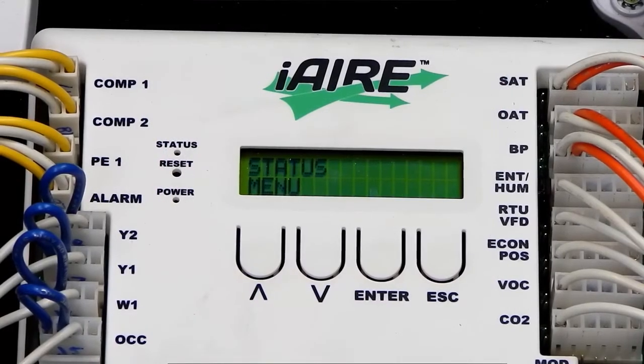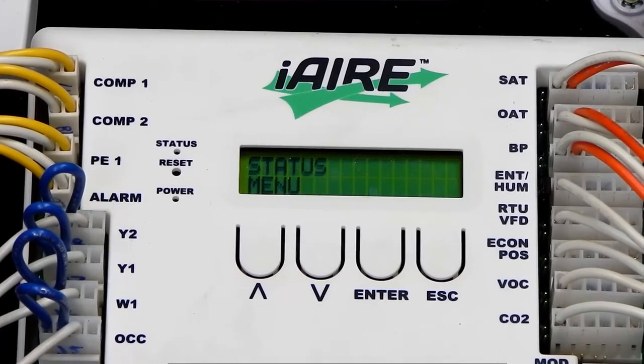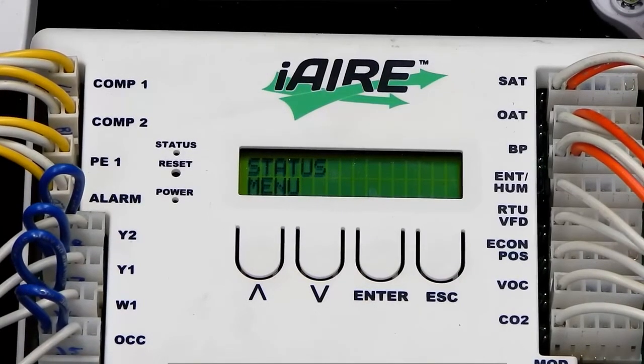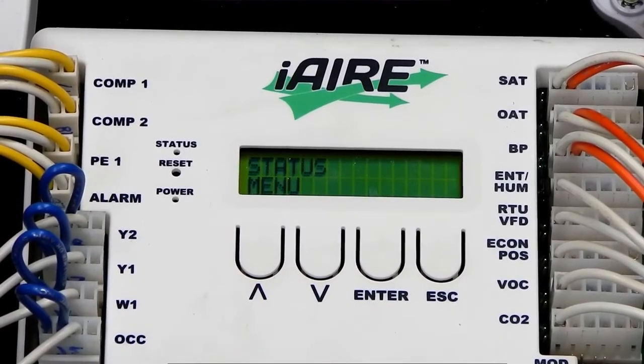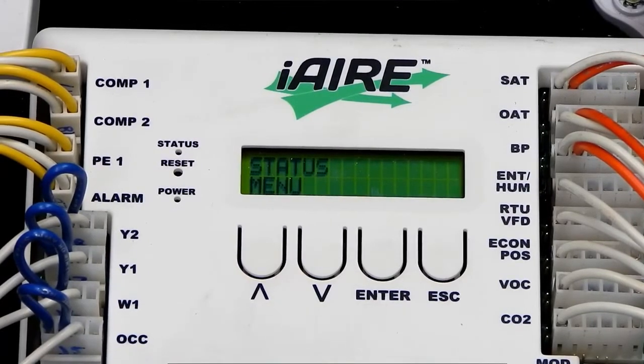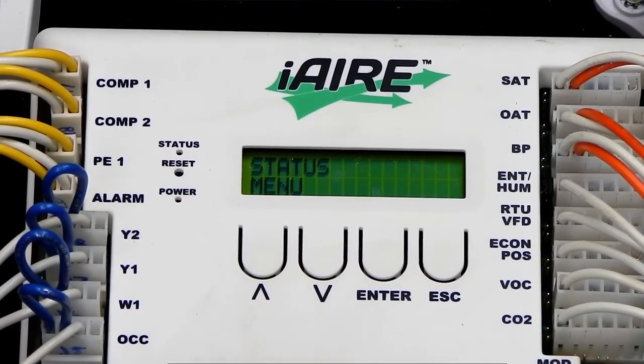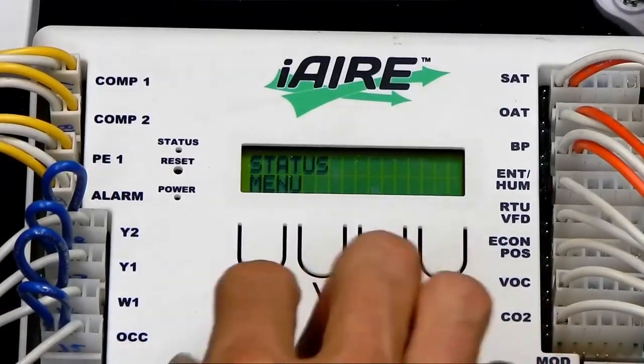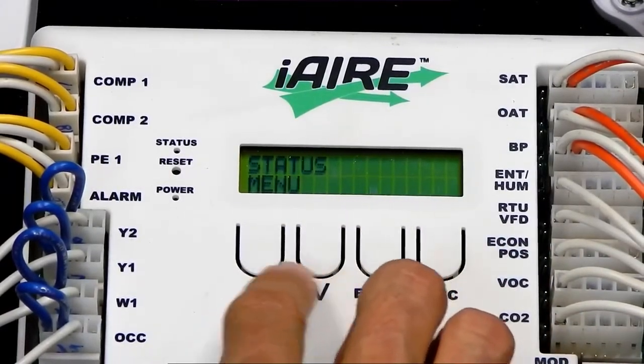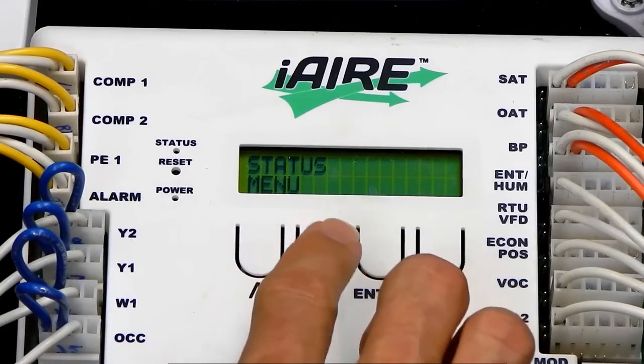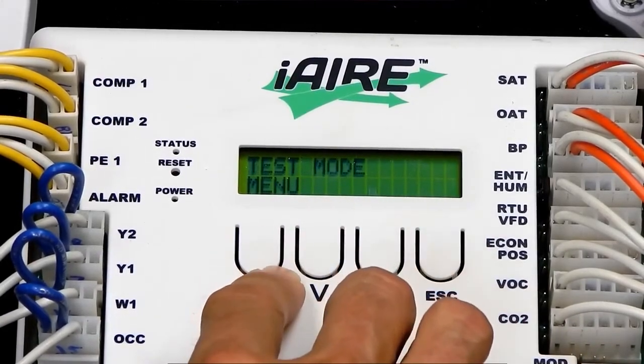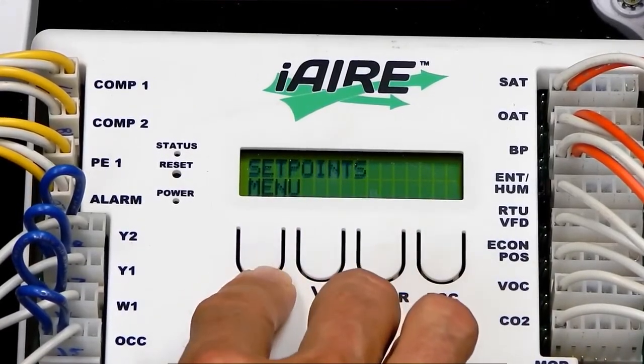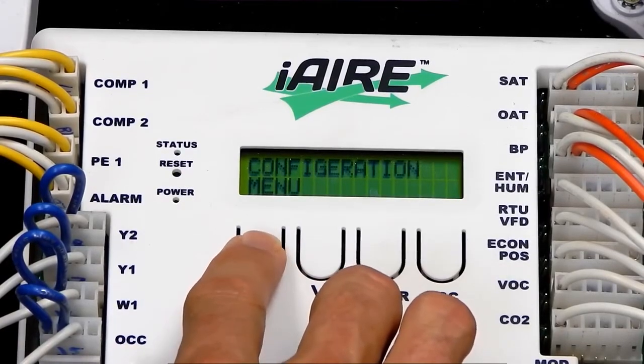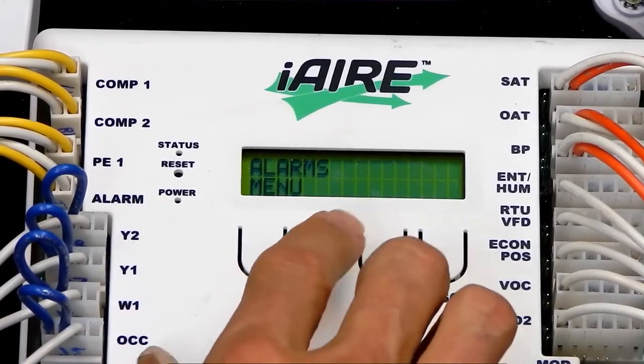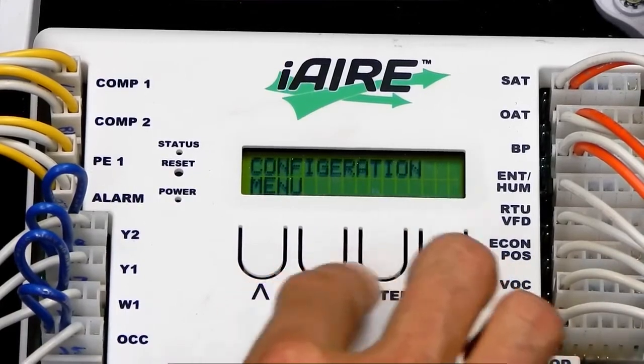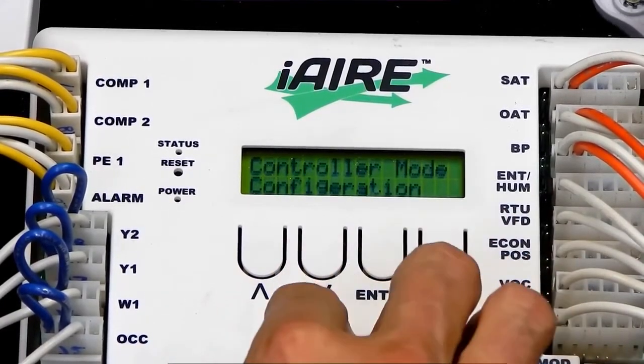The iAire controller is very easy to set up. You utilize the push buttons and the LCD to do all the interface. We're going to walk through setting up the unit in standard economizer mode. You'll start at the main menu, and there are several main menus in the controller: status, test mode, set points, configurations, and alarms. To set the mode you're in, you'd go to the configurations, hit enter.